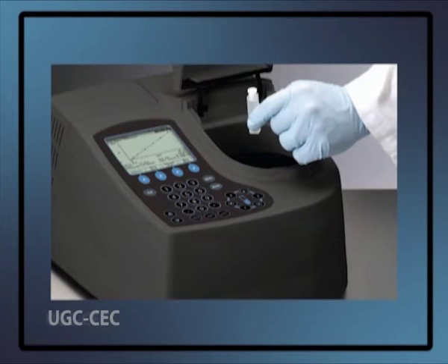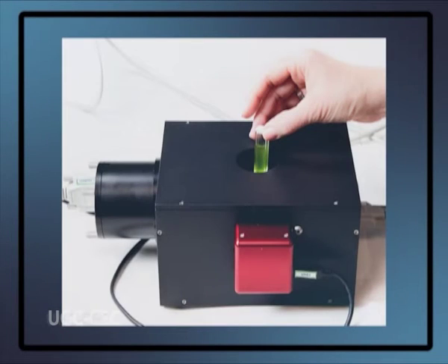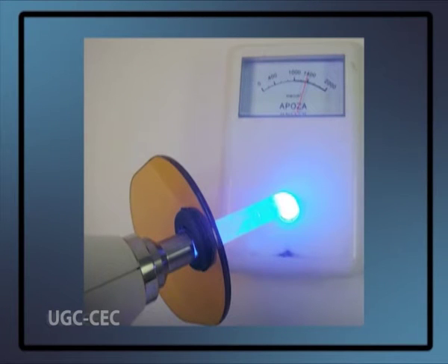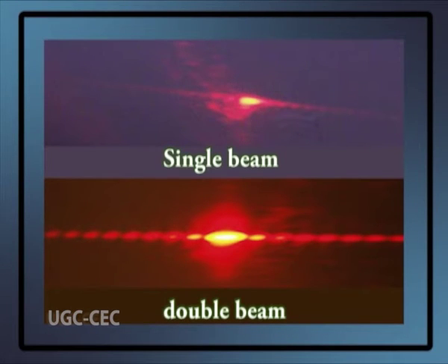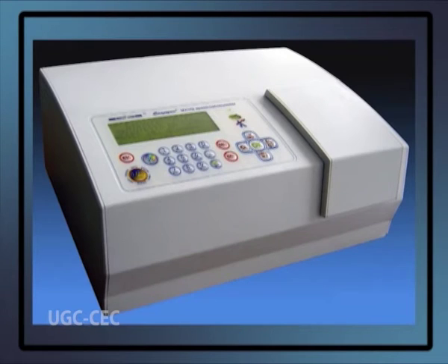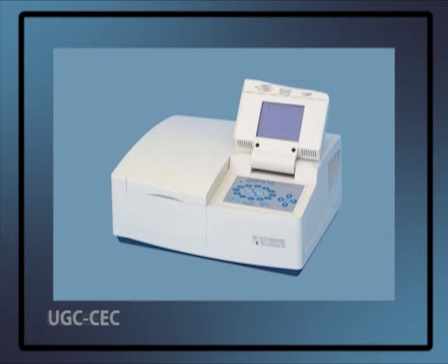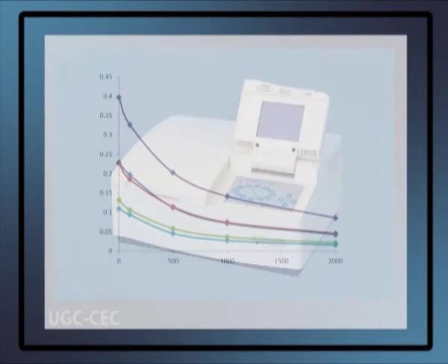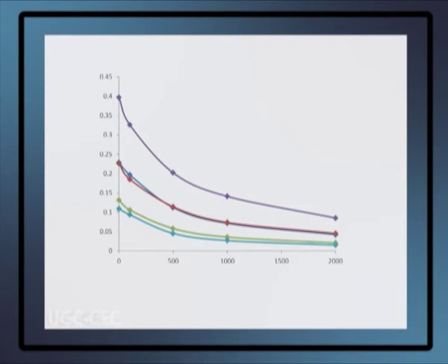A spectrophotometer is a photometer, a sophisticated type of colorimeter that can measure the intensity of light as a function of its wavelength. Single beam and double beam are the two major classes of spectrophotometer. The single beam spectrophotometer measures the relative light intensity of the beam before and after a test sample is inserted, and the double beam spectrophotometer compares the light intensity between its two light paths.